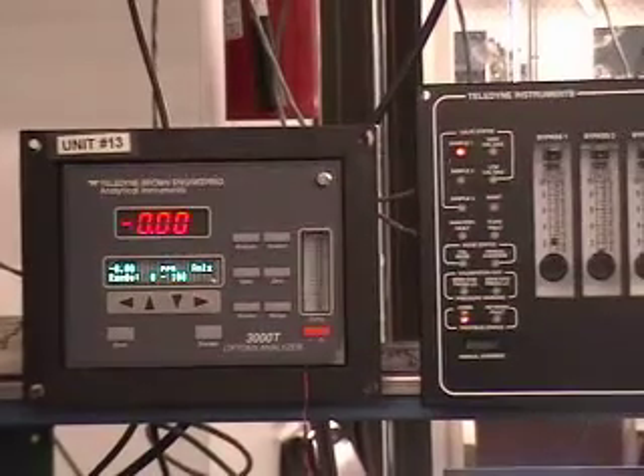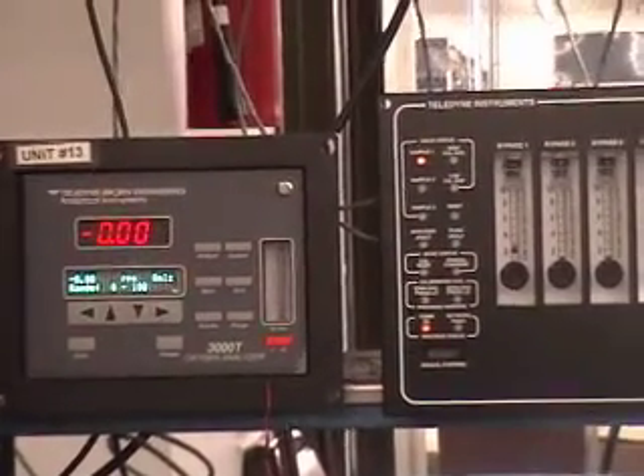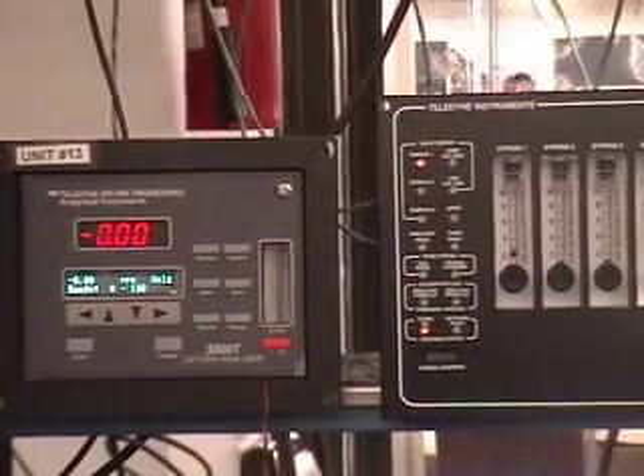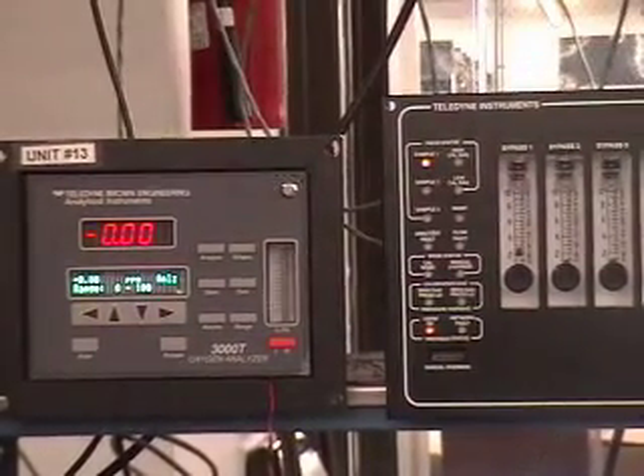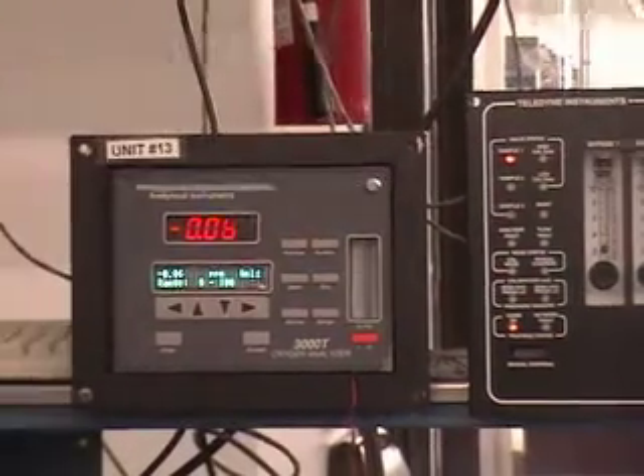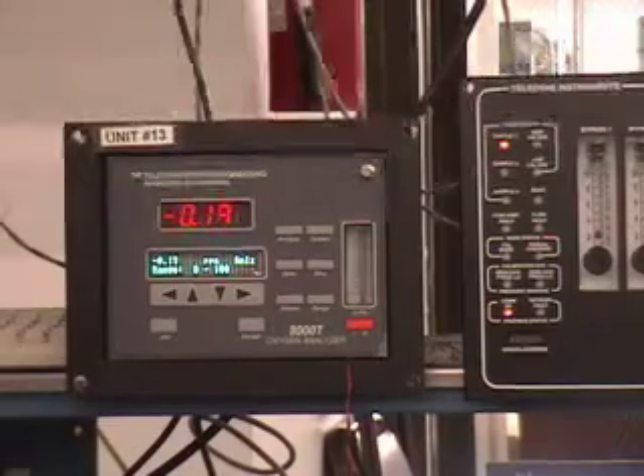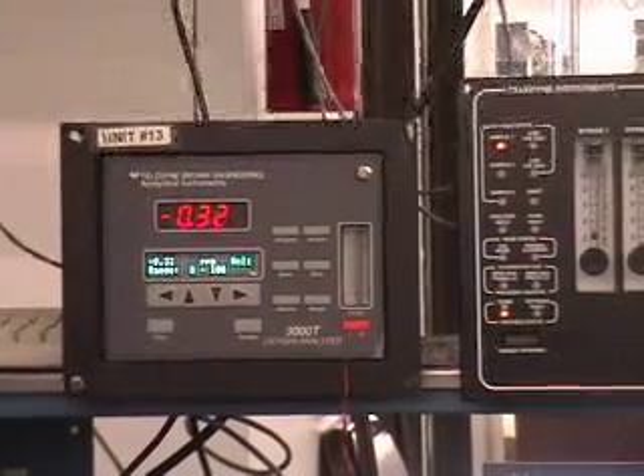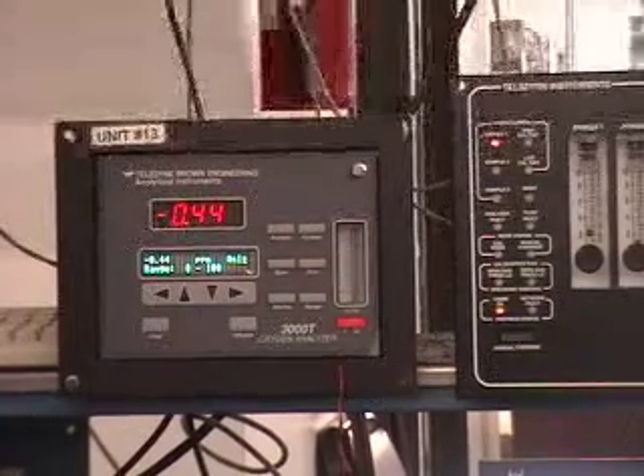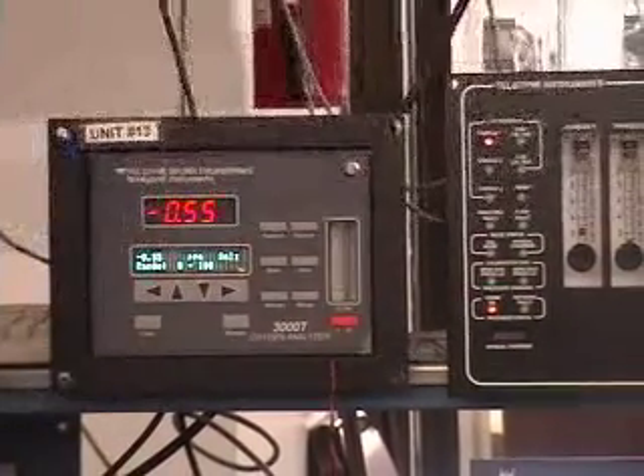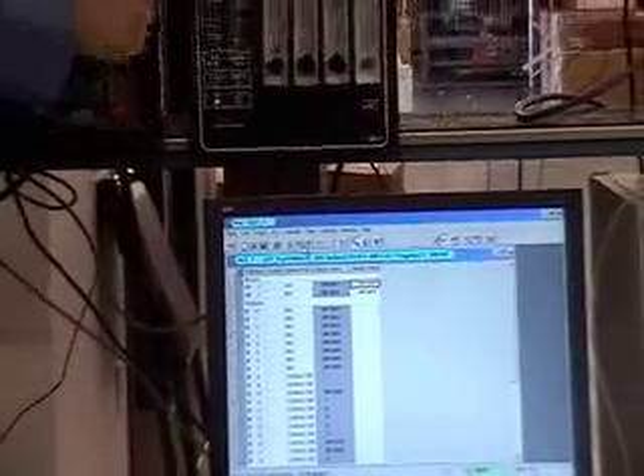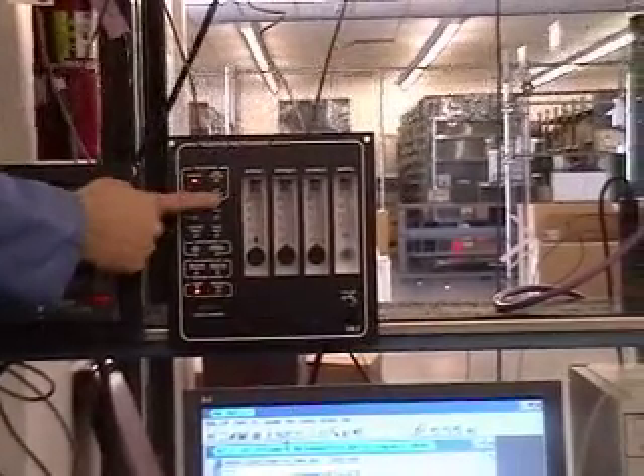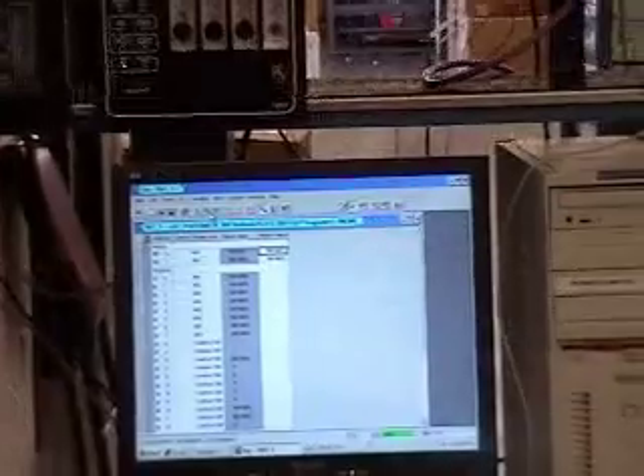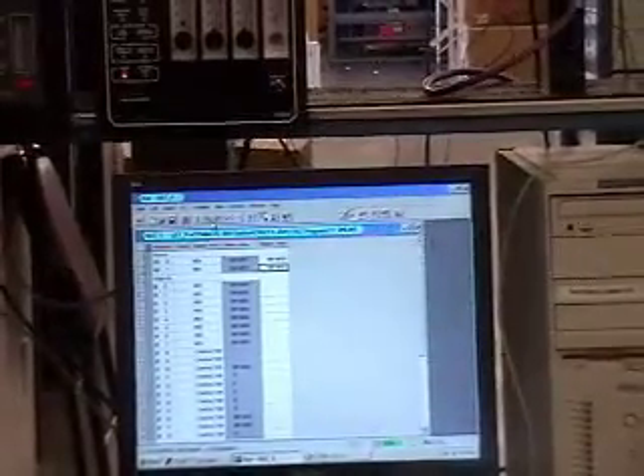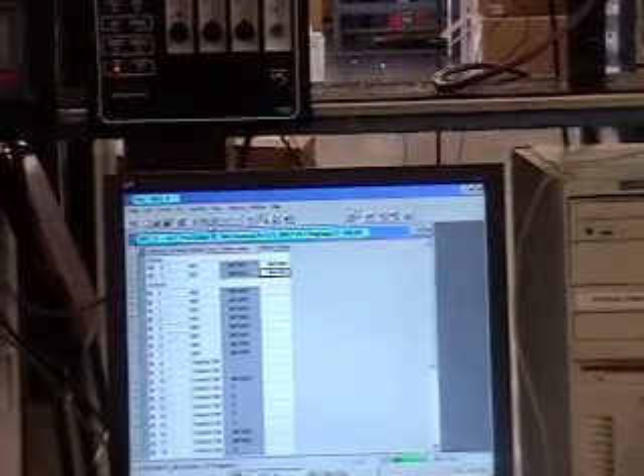Now we're going to do a span. For that, I'm going to change the cell simulator output so we can get some reading over here. So we should start seeing some reading coming out here. I'm going to wait a little bit so that you get some reading. And then I'm going to send the span command. The span command is basically going back over here. It's going to be 8. Okay, remember we're counting in binary: 1, 2, 4, 8. So that one's 8. I just typed it in, haven't sent it yet. I've got to send it.